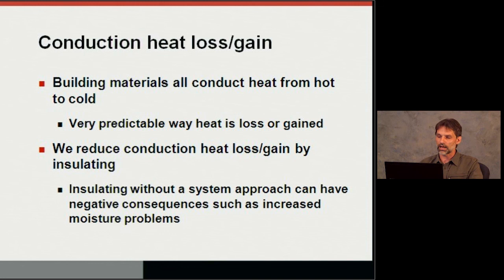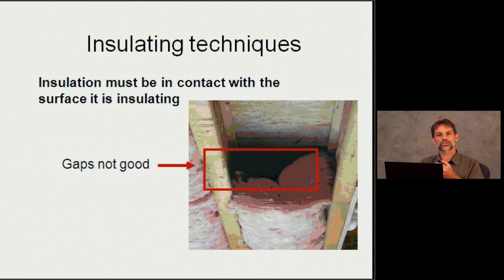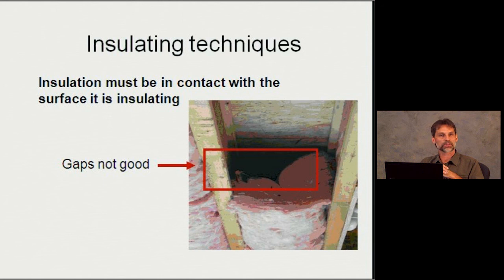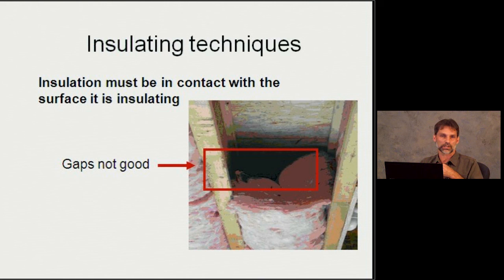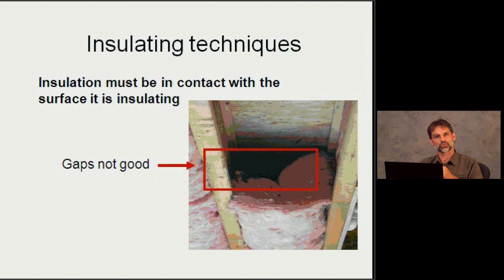Regarding insulating techniques: insulating without a good air barrier, or insulating poorly with gaps and voids, creates problems. Looking up at a floor system, a gap in the insulation does not allow for effective conduction heat loss reduction — the insulation needs to be in contact with the surface it's insulating. We might see this above garages or in cantilevered floors, where insulation has fallen or was never installed correctly. We can actually have miniature convective loops between the floor above and the insulation, robbing its effectiveness.